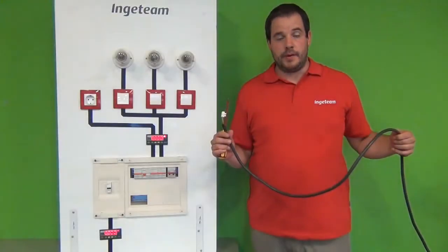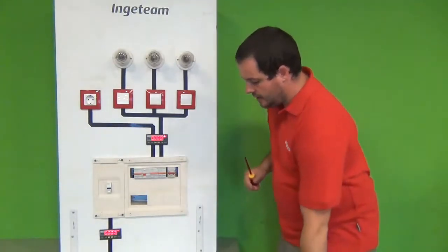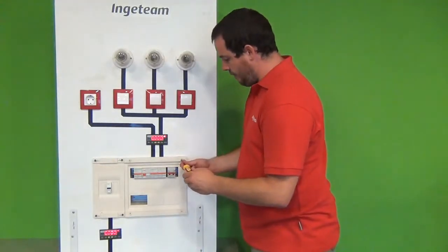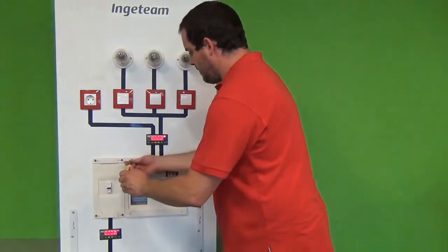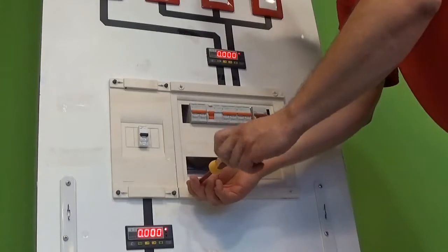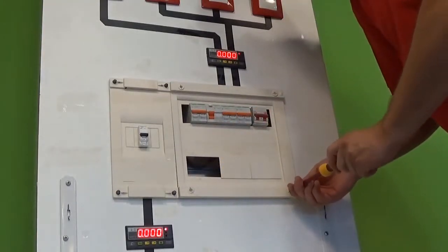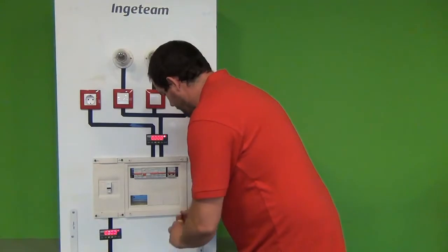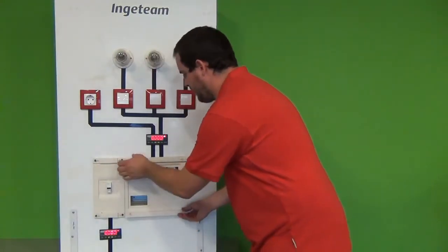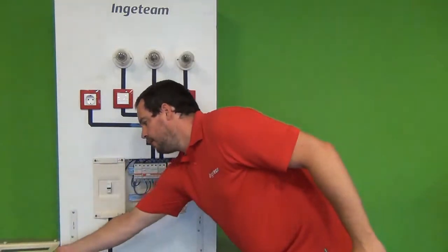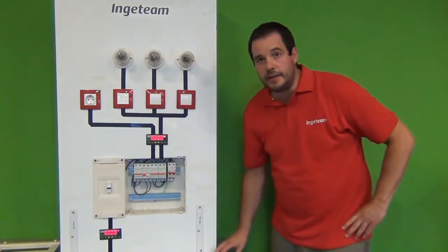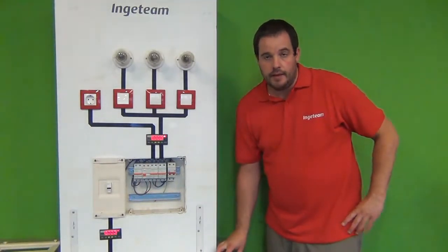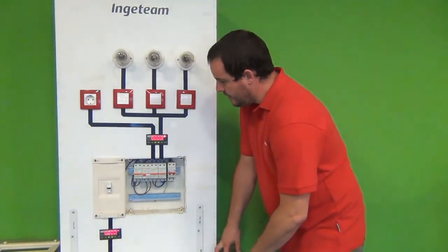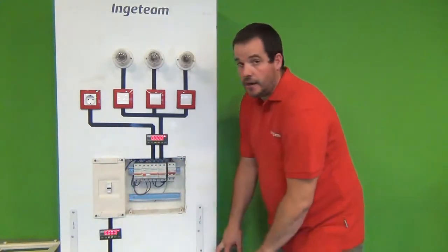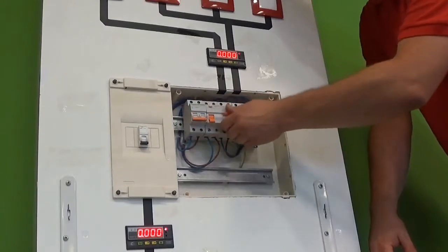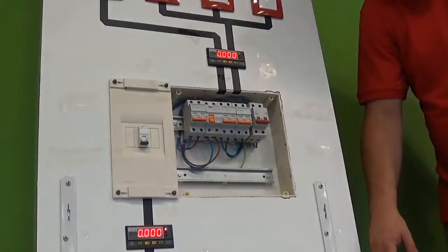The other end of this power cable is going to be plugged in this thermal magnetic breaker you see over there. First thing, I'm going to open the switchboard. Off. As you can see, this is the thermal magnetic breaker where I will plug the inverter, right? So the first thing, as you can see, all these protections are closed, so I'm gonna open them all so I don't have any problem.